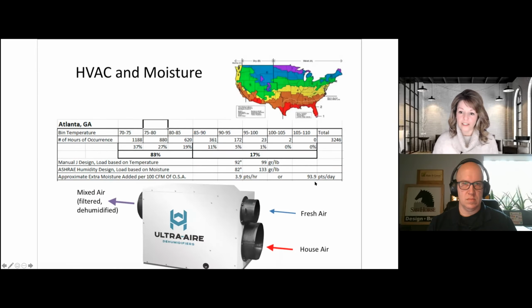Very interesting here, because what we have right here is the manual design load based on temperature. So that's that 92, our peak load for Atlanta. What's interesting is our ASHRAE humidity design is 82 degrees. So this means that when it's 82 degrees in Atlanta, it's typically when we have the highest dew points. But we're designing for the 92 because that's the temperature. So if we look over here, what Mike did is broke this down in number of hours of occurrences. So 83% of the time in Atlanta, the temperature is 70 to 85 degrees.